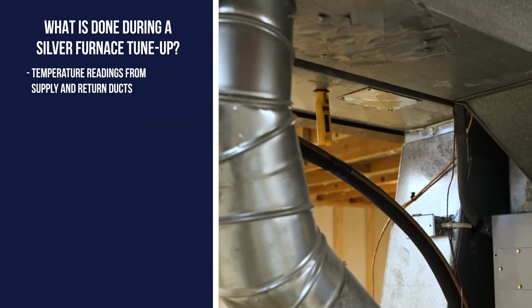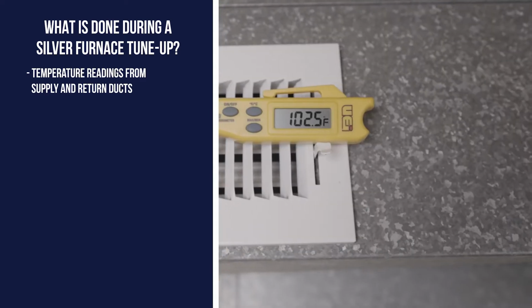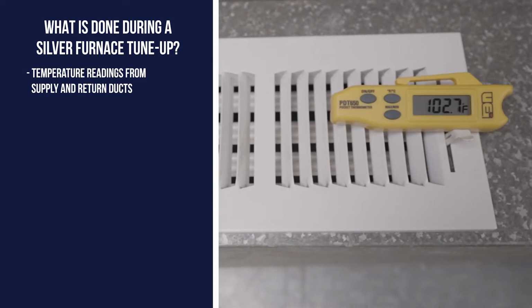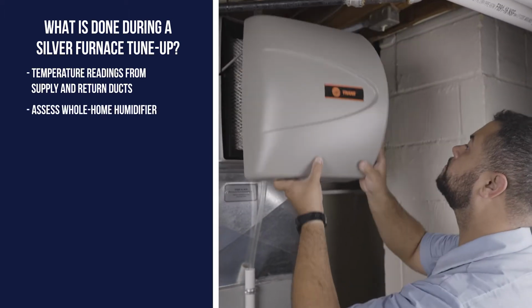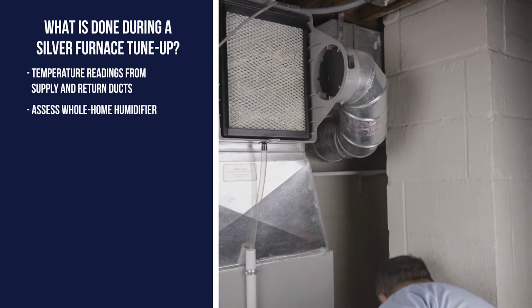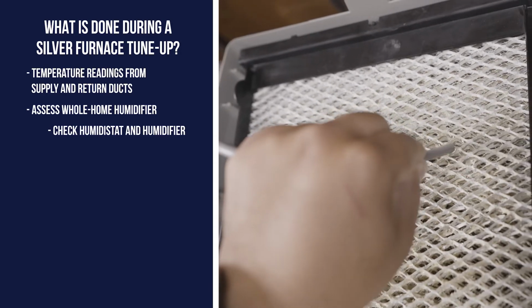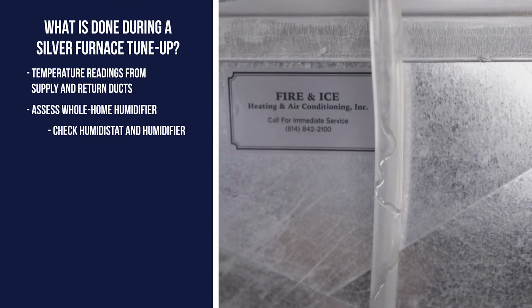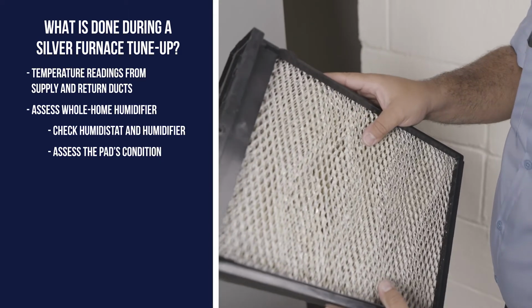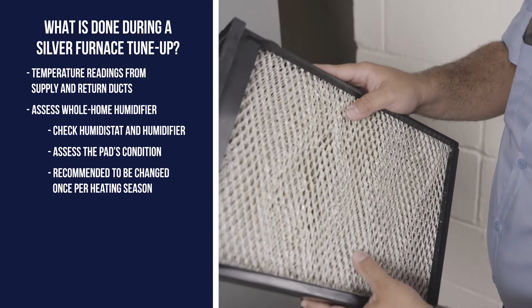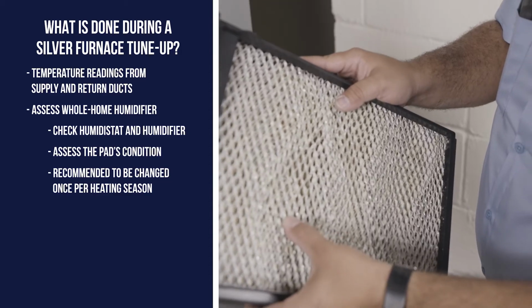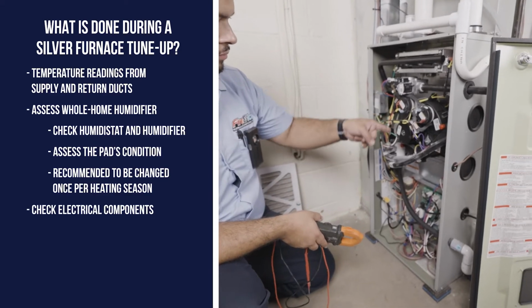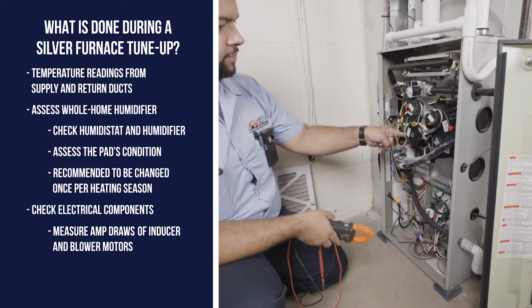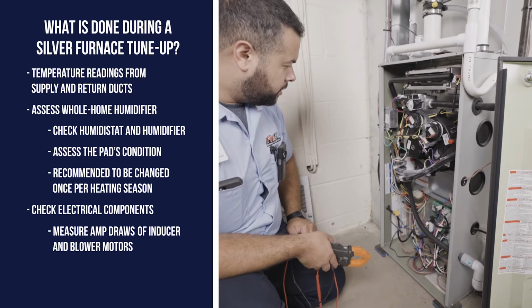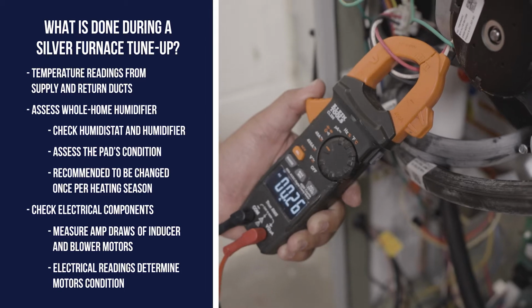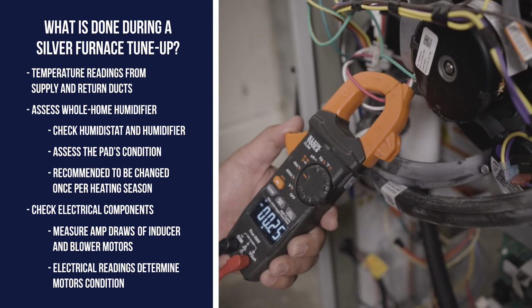Next, we take a series of temperature readings from both the supply and the return air ducts to see if they are within the normal ranges for your furnace. If your home has a whole house humidifier, we'll check that too. We'll make sure that both the humidistat and the humidifier are working and draining properly. We also assess the humidifier pad condition. Generally, we recommend replacing the pad once per heating season. Next, we move on to the electrical components. We'll take note of the amperage draw to both the blower motor and the inducer motor. These readings help us determine if the motors are operating normally or in need of repair.